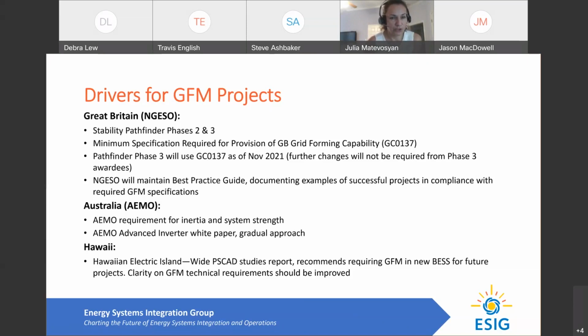In AEMO, there's a requirement for inertia and system strength provision in certain parts of the grid. This has to be procured by a transmission or distribution service provider, so this can also be viewed as an incentive for grid forming inverters to participate and provide this service. AEMO also recently released an Advanced Inverter White Paper, identifying grid forming inverters as a needed component going forward with more inverter-based resources on the system. They propose a gradual approach where grid forming inverters are implemented on the grid, helping local parts first, then gradually using this capability more widely, and providing black start at the final stage. The Hawaii Electric wide PSCAD studies report, recently released, also recommends requiring grid forming inverters in new battery storage projects going forward. We can jump to the next slide, and I'll go through conclusions very quickly.